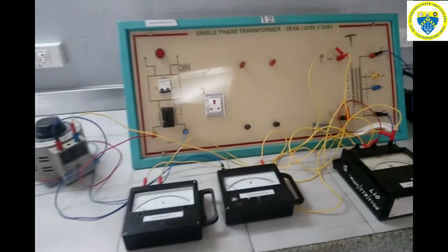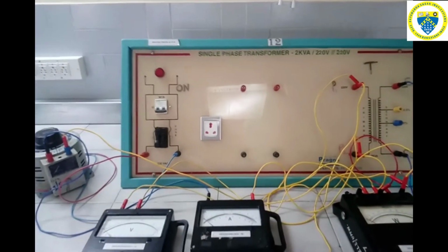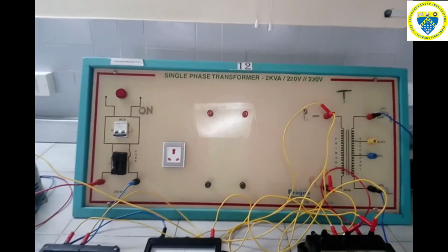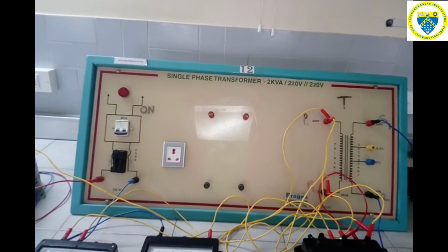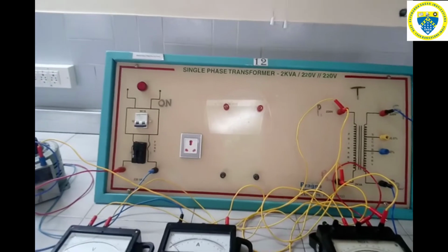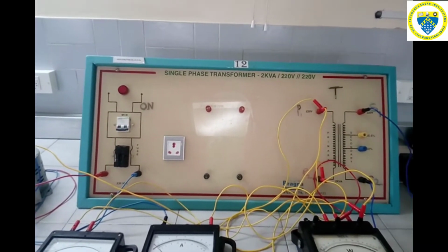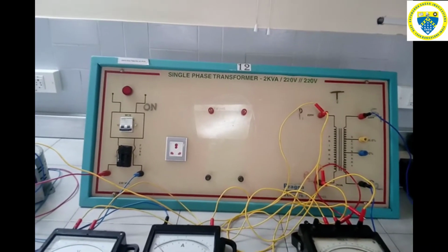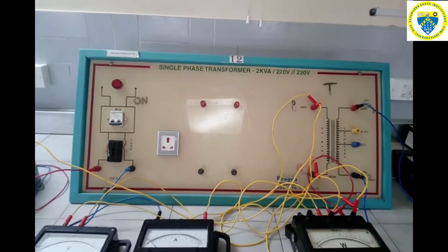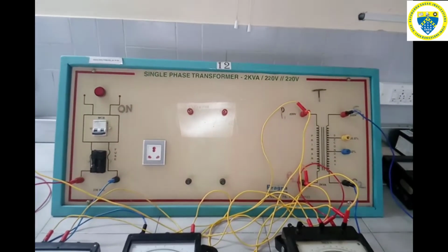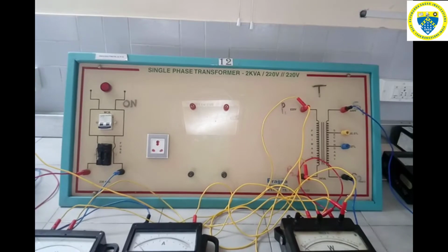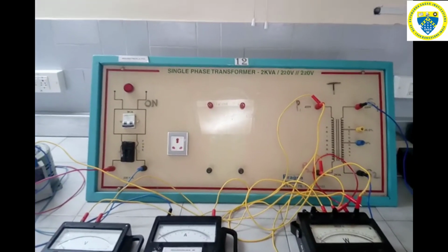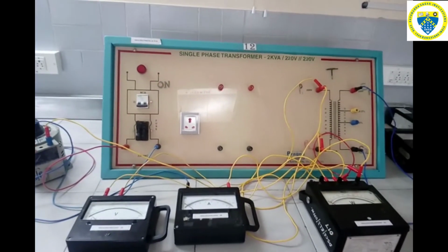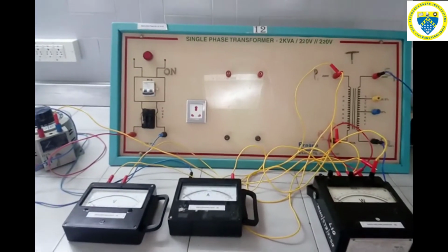The same procedure is followed, but instead of applying the rated voltage of 220 volt as we did in the open circuit test, here for the short circuit test we are applying the rated current, that is the full load rated current, which should be calculated before conducting the experiment. For this rating of 2 kVA and 220 volt, the full load current for this transformer comes out to be 9.09, around 9.1 amperes.